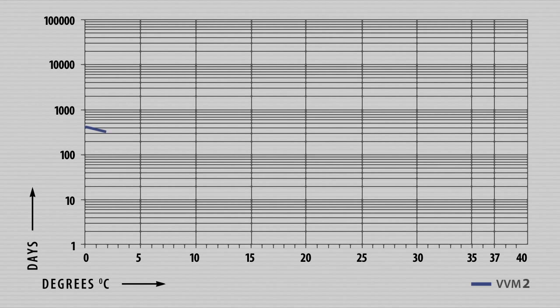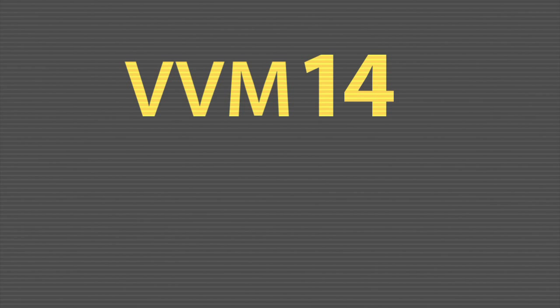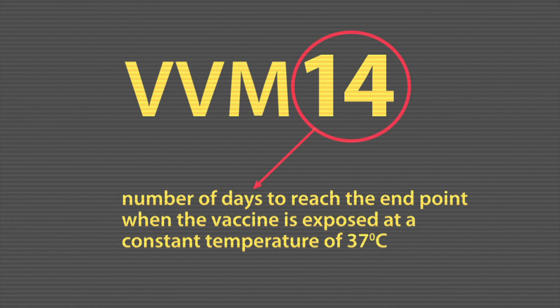The thermostability data of all vaccines can be matched in four VVM types defined as VVM2, VVM7, VVM14, and VVM30. The number characterises the number of days to reach the end point when the vaccine is exposed at a constant temperature of 37 degrees.